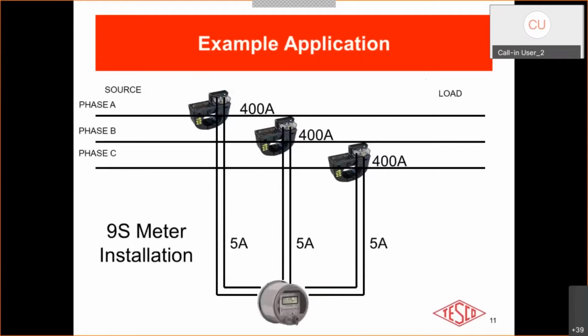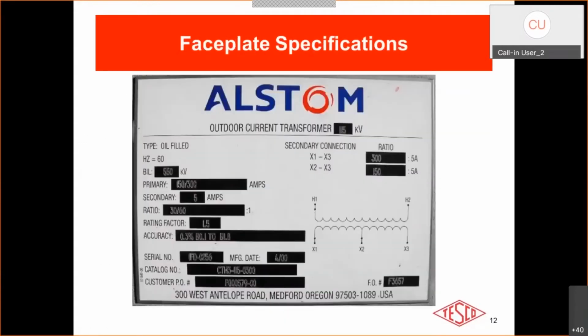For these test examples, we will use an example application here, a 9S meter installation, which utilizes 3 CTs, 1 for each phase, and their secondaries run to the transformer rated meter. Everything that you need to know for testing a CT is located on the faceplate of the CT, just like in meter accuracy testing.